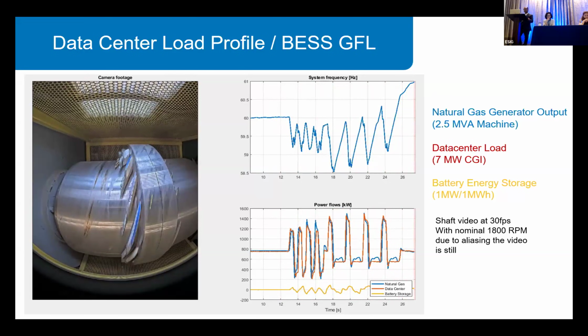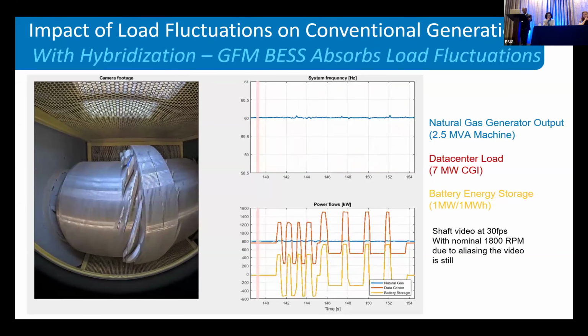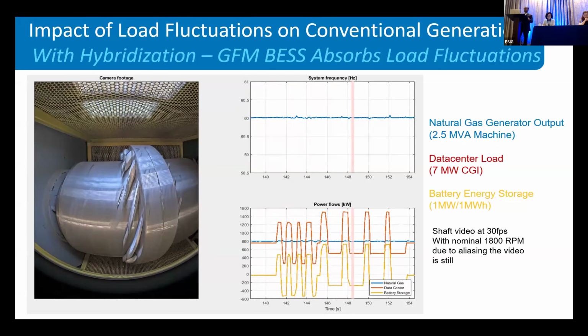In the next case, we tried using our battery energy storage to take those high frequency oscillations out, so that the generator only sees the base impact of the data center load. As you can see, it was pretty smooth, and you hardly see any movement on the shaft, because it's being taken care of by the energy storage.